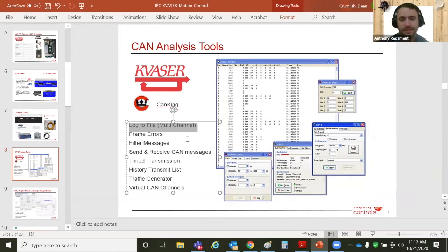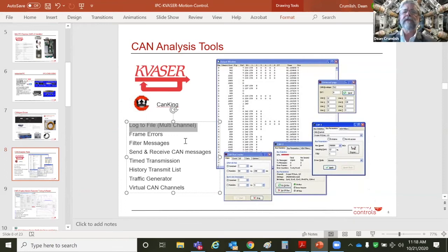Frame errors. Yeah, we look for timing issues. Usually you debug by reading PDOs, and so you want to know what the PDO mapping is on a CAN network. So you want to be able to tell when you're sending SDOs and when a sync message is sent. So there are all these different aspects to the DS402 protocol, and that's what you'd want to see in a CAN log. Yeah, that's good. Thanks for that, Anthony.